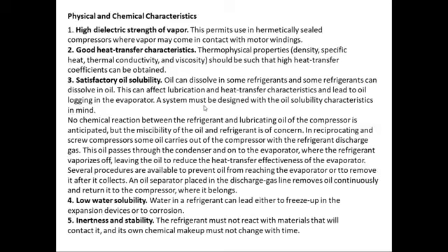If some oil escapes from the hermetic compressor, then it can be captured just after the compressor, before it goes to the condenser, and then returned to the compressor. So that is the story here. An oil separator placed in the discharge gas line removes oil continuously and returns it to the compressor where it belongs.